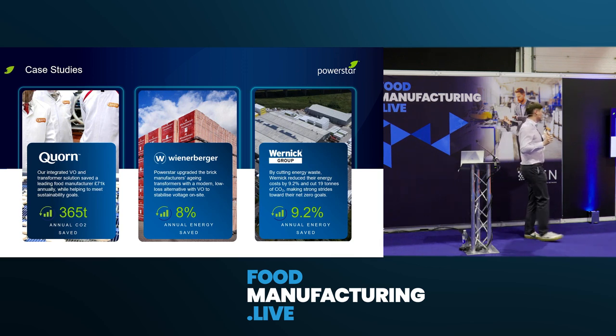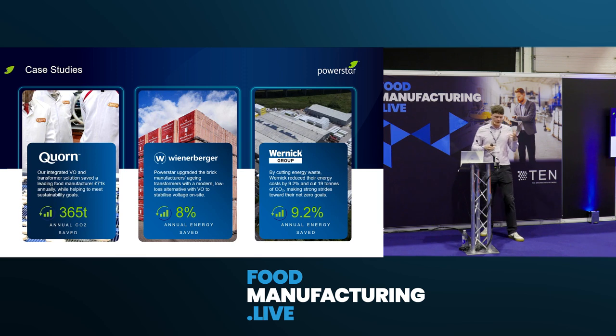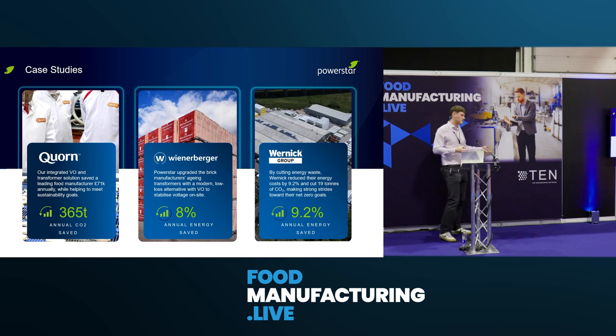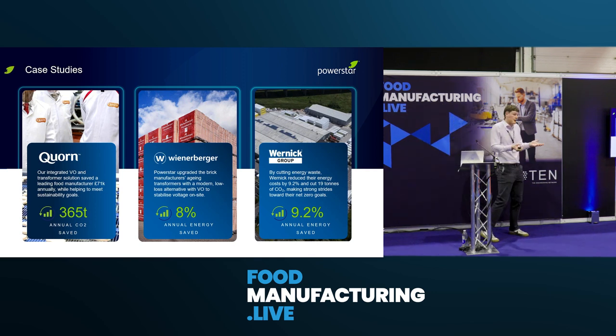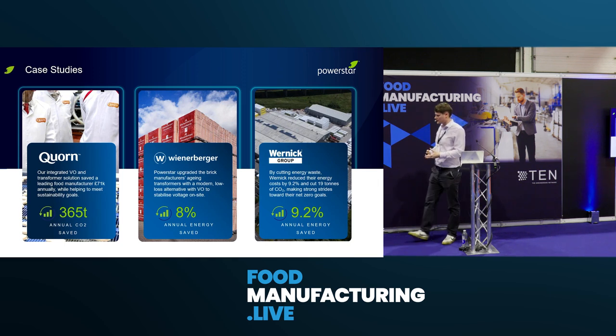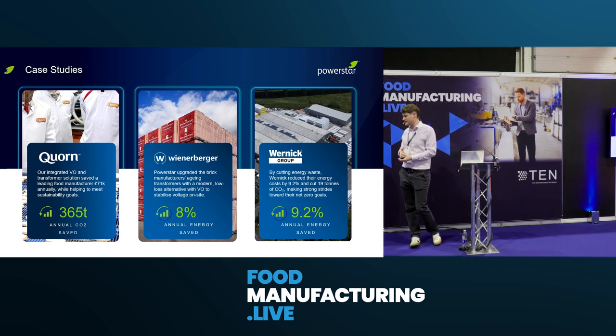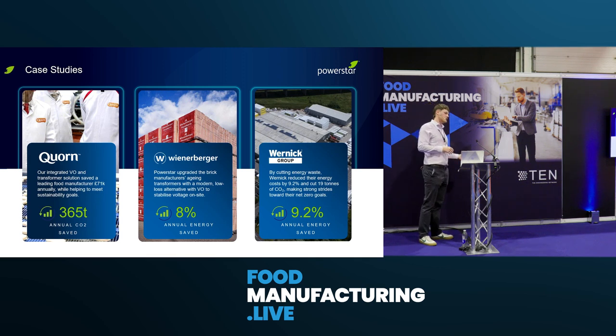Wienerberger is a brick manufacturer with some real intensive process equipment using a lot of energy. This is where we start talking about a mixed load application. The heating elements used for baking the bricks didn't really have much effect, however the mixture of equipment on site - the motors, the various pumping systems - generated savings. We averaged an 8% energy saving throughout the year on just one of their sites.